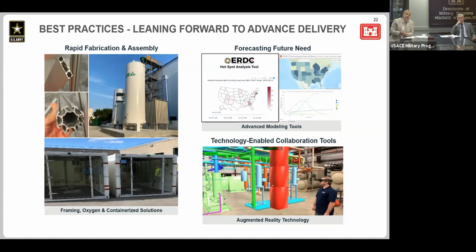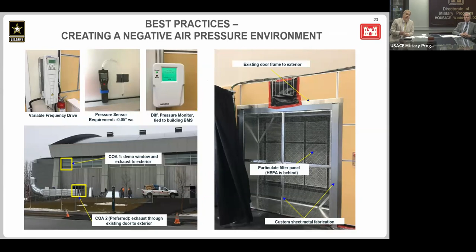We created negative pressure at 0.05 inches of water column. To maintain that pressure, we used variable frequency drives on the fan motors and pressure monitor sensors with alarms, so that once there was a fault in pressure, we knew instantly. We utilized existing windows and doors for exhausting the filtered air outside.